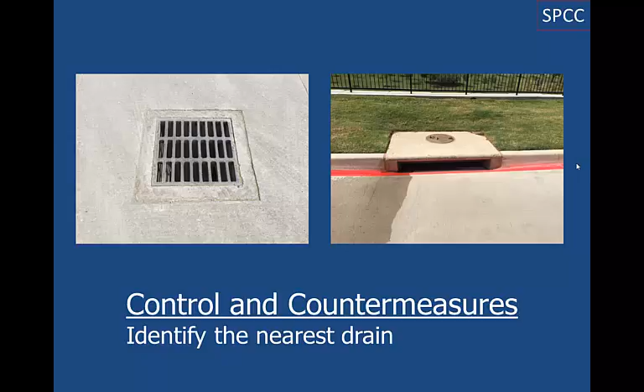So here we are in the field, and if we had a spill beside this transformer, first look for the nearest storm drain downgrade from the spill. You can see it over about 10 feet away. So this is where you'd want to place the wattles and absorbent material. You could use the pads on the spill or to cover the storm drain, and then use bagged absorbent on the spill itself.